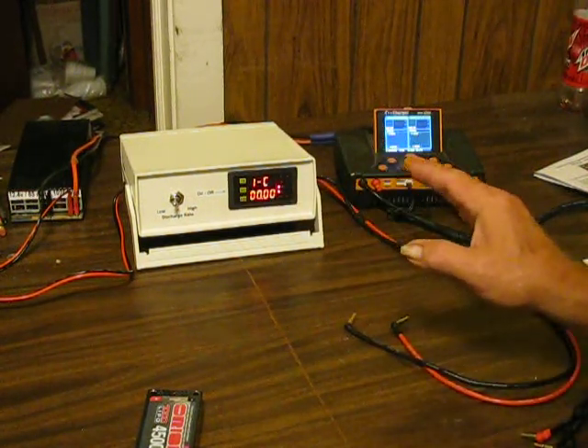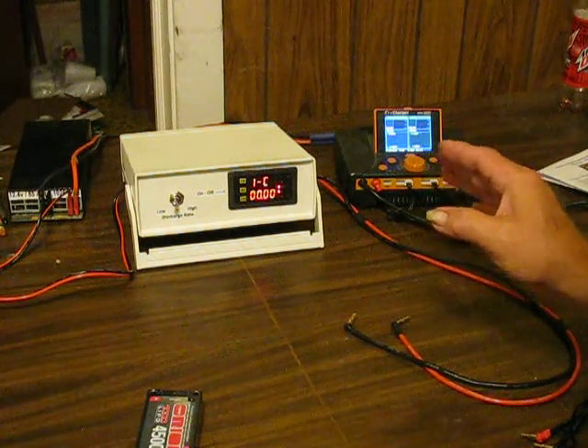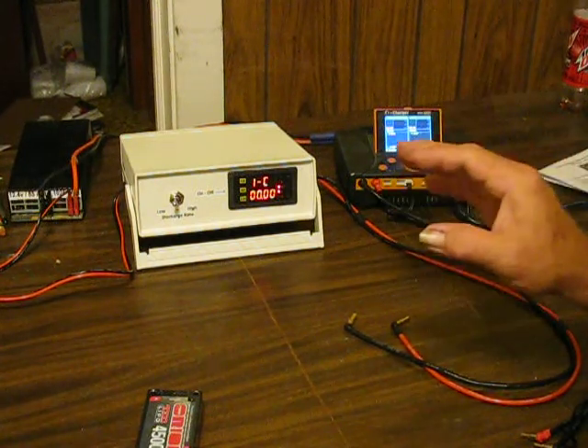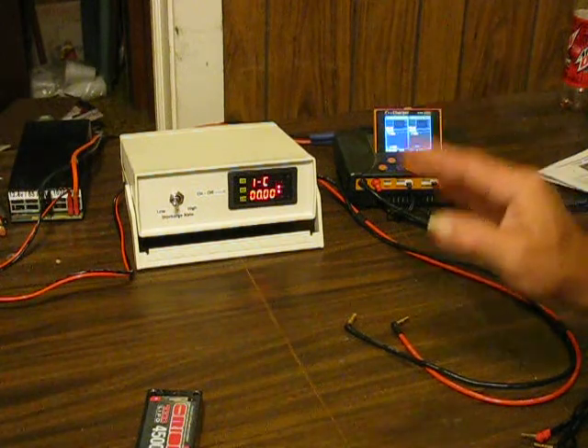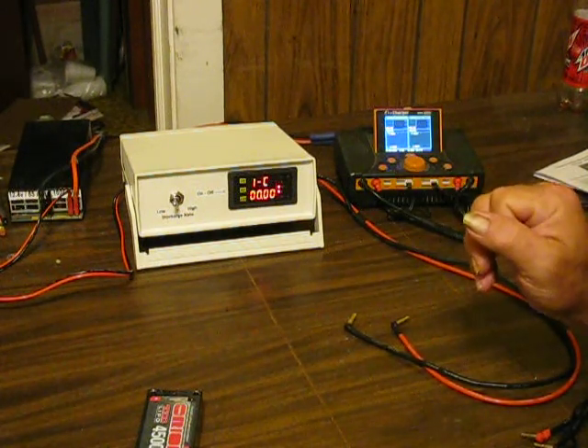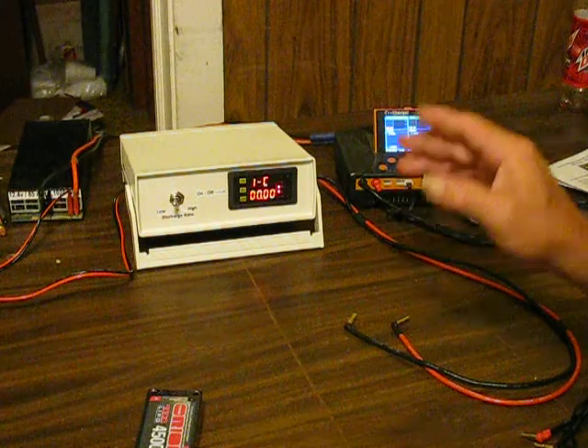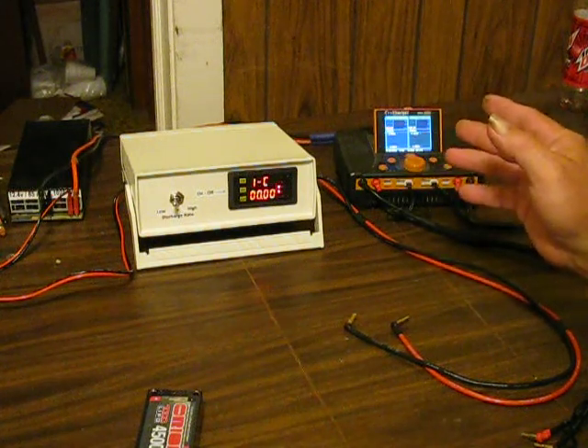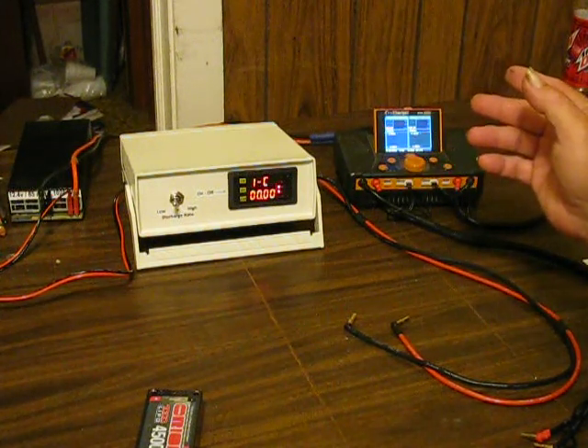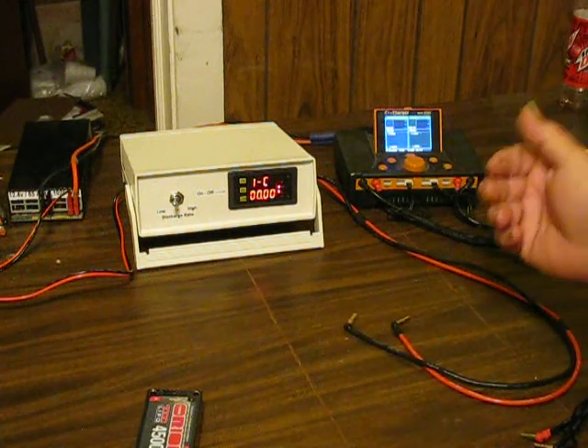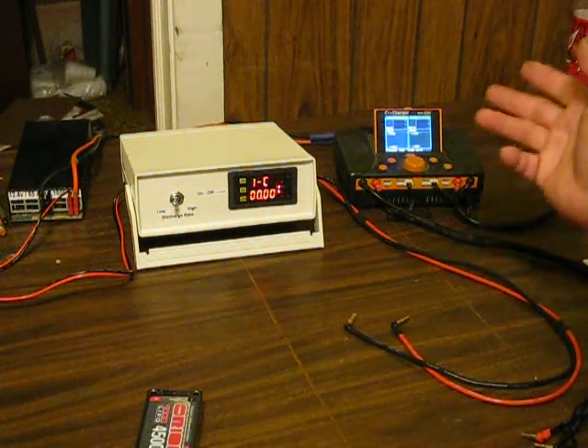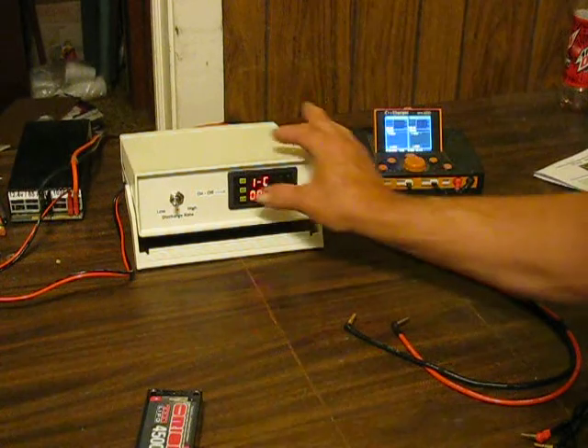That should have your amperage calibrated pretty close. I've never checked the upper range on it. I know it's pretty close, so I've never messed with the upper range. But if you wanted to get an ammeter, a 25 amp meter, and hook it in series, it's your choice, but it's not necessary.